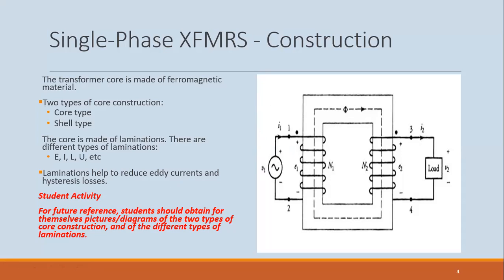So the laminations are basically there to reduce losses, and the losses manifest themselves in the form of heat. Normally a transformer that is energized will emit some heat, so especially with large power transformers, if you're nearby, you will feel the heat. Because of this heat, damage can be caused to the windings, so methods of cooling the transformer exist. There are different methods of cooling the transformer, which we'll get into later.